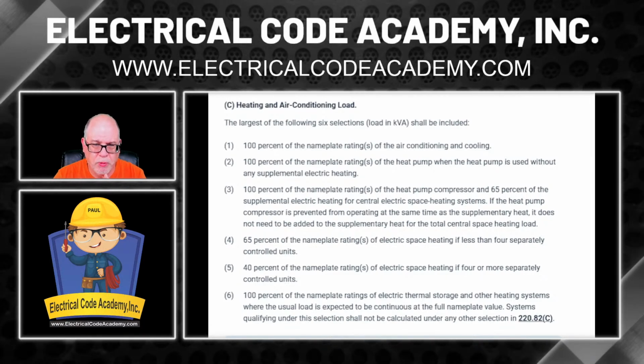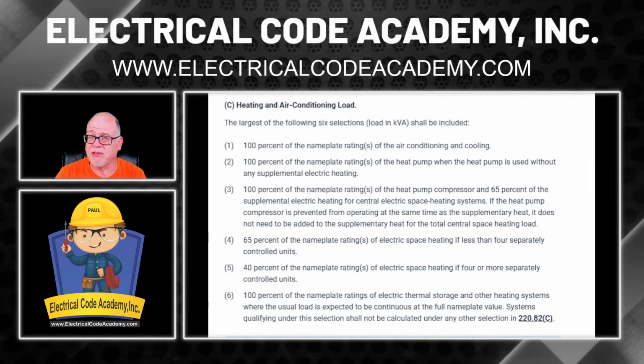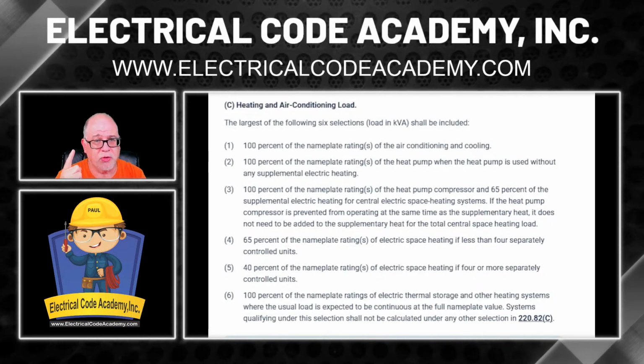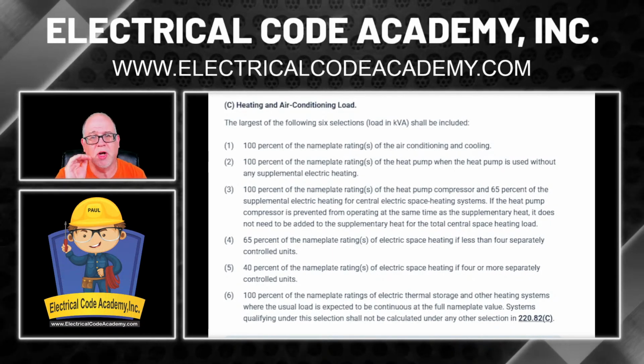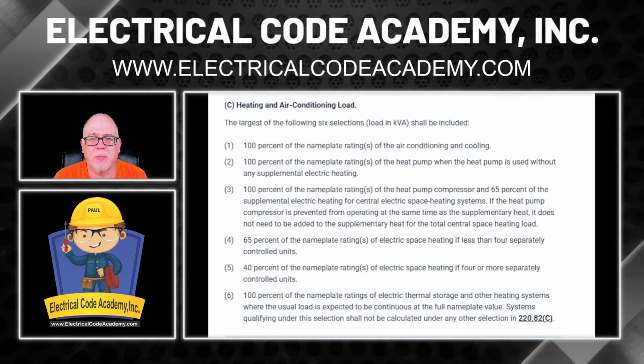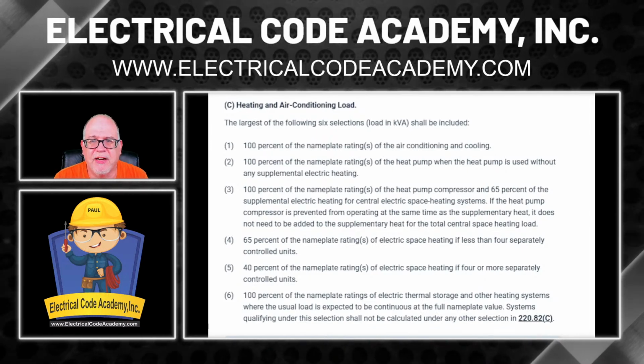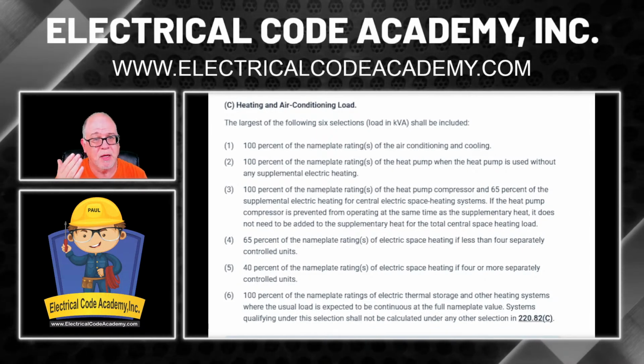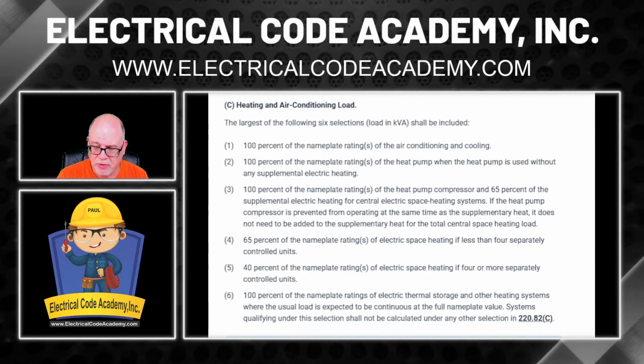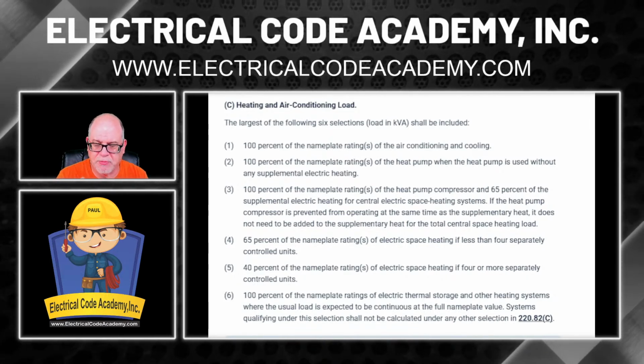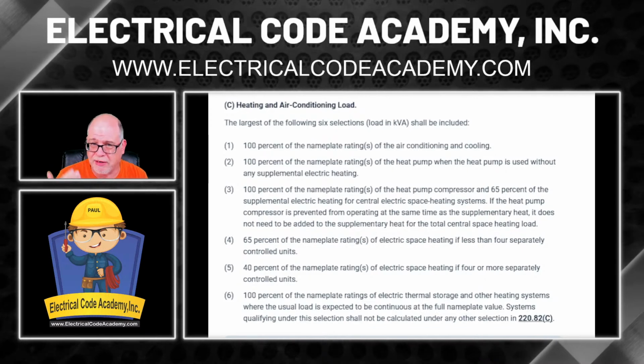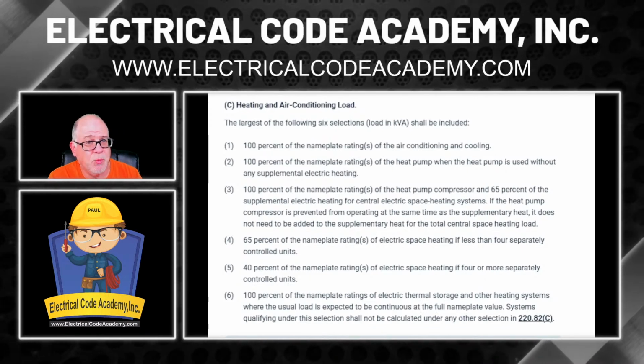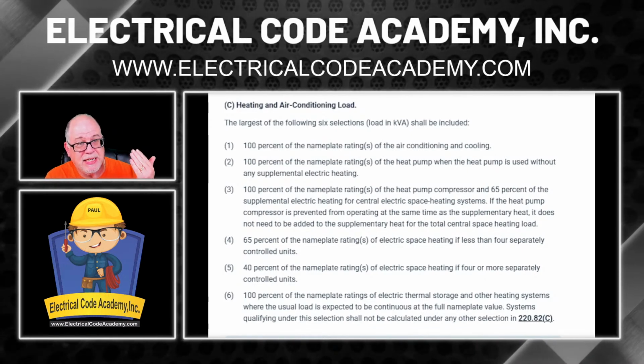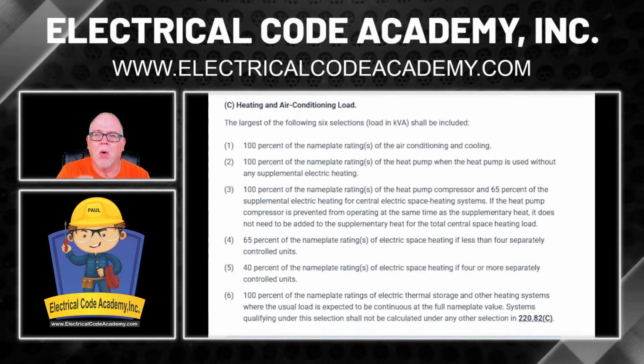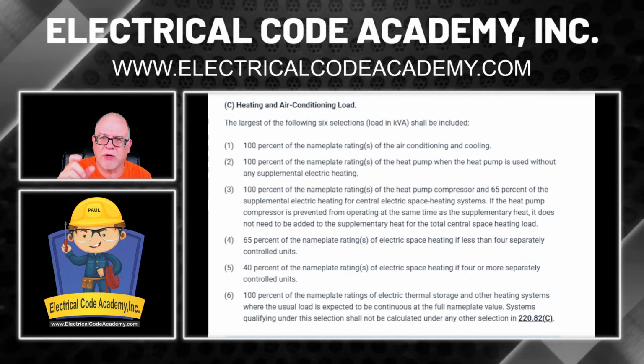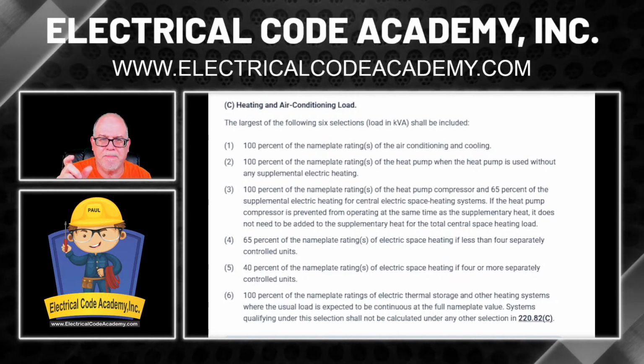Well, there's 1, 2, 3, 4, 5, 6. Well, we're only going to use 2 of these. Obviously, one's going to deal with air conditioning, and the other is going to deal with the heat. Well, number 1 on this list says 100% of the nameplate ratings of air conditioning and cooling. Well, we already know what our air conditioning is. We had 2 of them at 10.5 amps and 3 of them at 7.2 amps. So we know what our air conditioning is. And we know our heat. There was 6 of them at 3 kW each. Okay, so we know that when it comes to the AC, we're going to take their full value at 100%.